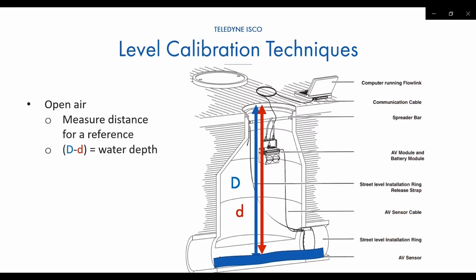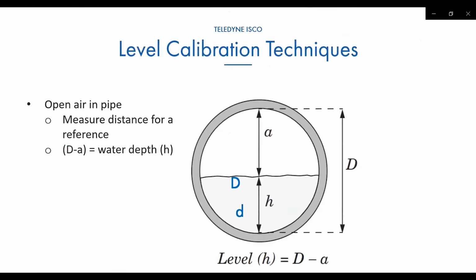I've seen multiple techniques on how people do this. One, you could take a rope or a string, tie a bolt to the bottom of it, and just lower it down. When it starts to hit the top of the water, you're going to see that the string moves. Measure the length of that string to give you the overall depth, or just use a tape measure. Once the top of that tape hits the water, you can get your overall distance and then calculate your flow rate or your level. It's similar with the in-pipe calibration, exact same thing. You want to measure from the ID of the pipe, and then you measure the open air from the top of the pipe to the top of the water to then calculate your water height.